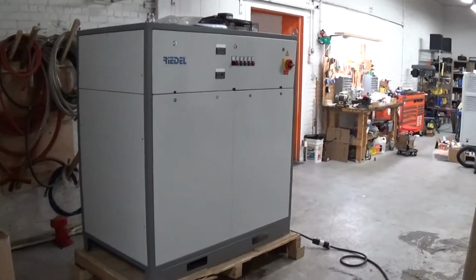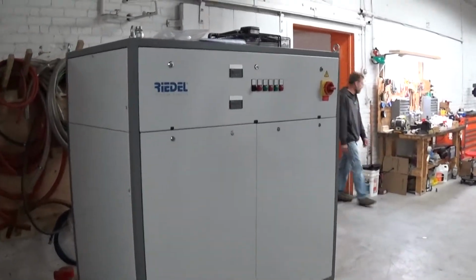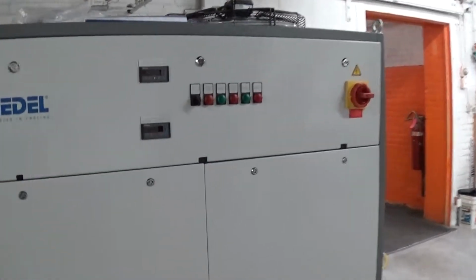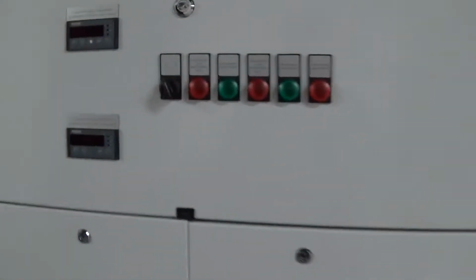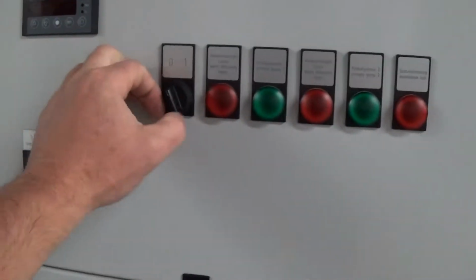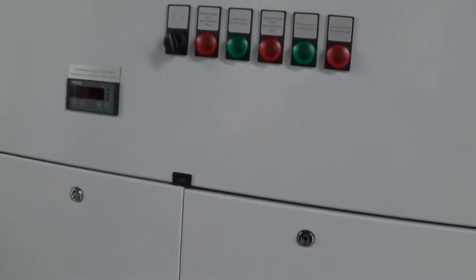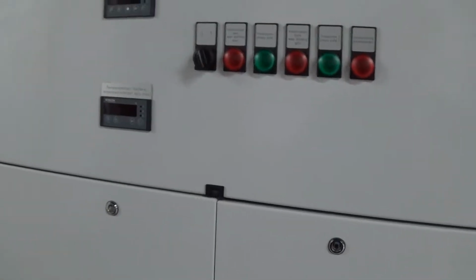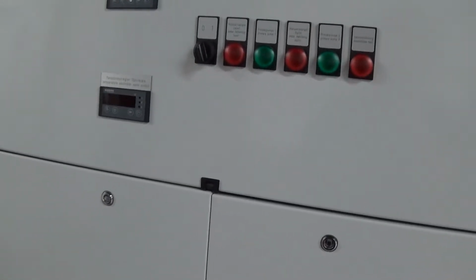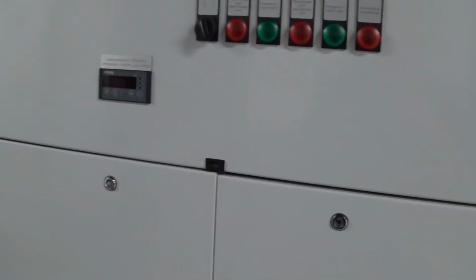This is our video number 2 for this Riedel 6-ton air-cooled chiller. We're going to go ahead, I put the side covers on as mentioned. We already have power to the unit. When you first get this unit, as long as there's power to the unit, the 2 compressors have crankcase heaters around each one. You should leave that on for about 12 hours before you try to turn on and actually start chilling.